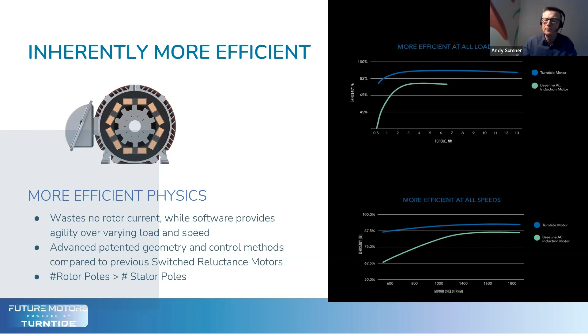The other 2 reasons are the characteristics of the motor. Traditional motors, if not running at their design torque, become significantly less efficient - that's the top right graph, the blue line being us, the green line being traditional induction motors. The bottom right-hand graph is speed. Most of your buildings will have HVAC motors controlled by VSDs or inverters, variable speed drives. The problem is as they slow the motors down, they become significantly less efficient. The blue line shows that we maintain our efficiency, and that's where the significant savings come from.